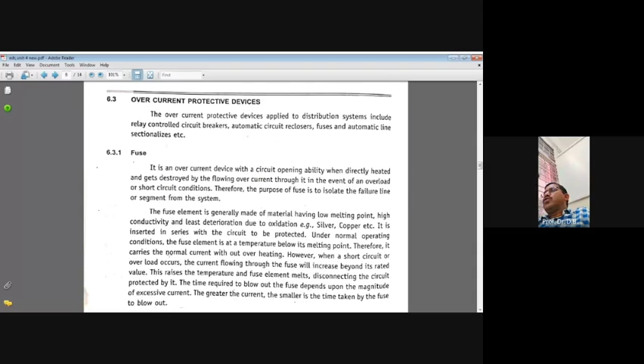You know very well the basic function of a fuse. A fuse is an overcurrent device with a circuit opening ability, directly heated and destroyed by the overcurrent flowing through it in the event of an overload or short circuit condition. Therefore, the purpose of a fuse is to isolate the failed line or segment from the system. The fuse element is generally made of material having low melting point, high conductivity and least deterioration due to oxidation, meaning silver, copper, tin, lead, and alloy materials are used for manufacturing. Okay, you know very well the advantages of fuses.